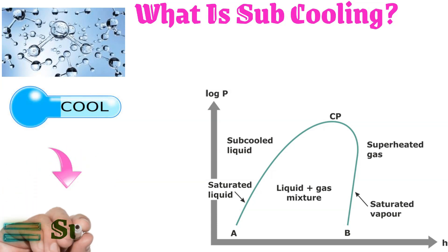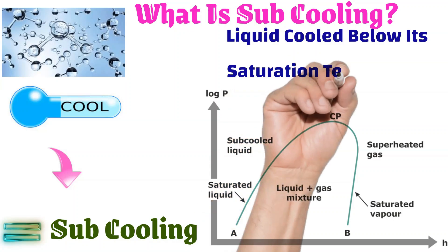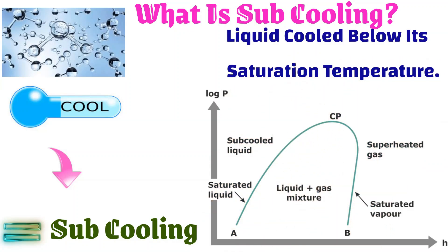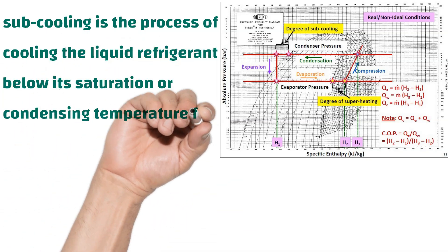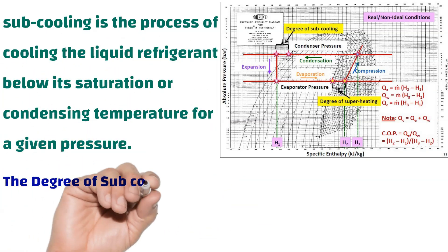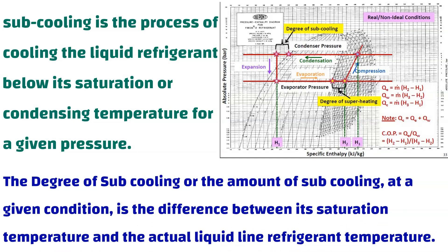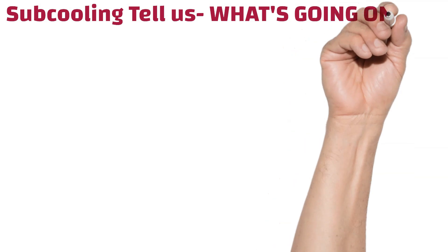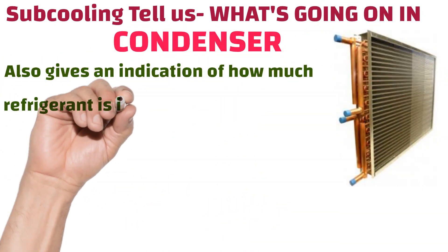Sub-cooling is the process of cooling the liquid refrigerant below its saturation or condensing temperature for a given pressure. The degree of sub-cooling at a given condition is the difference between its saturation temperature and the actual liquid line refrigerant temperature. Sub-cooling tells us what is going on in the condenser and also gives an indication of how much refrigerant is in the condenser.